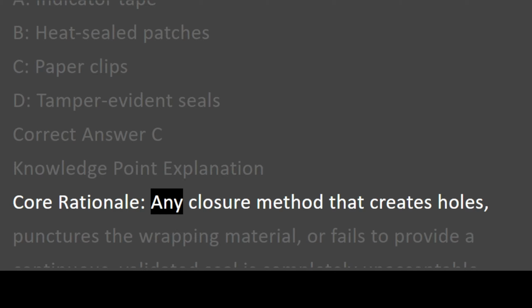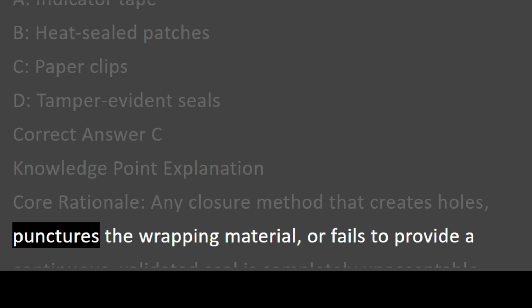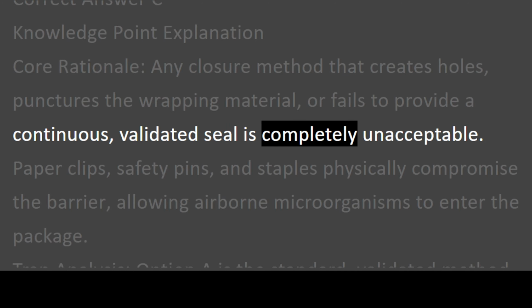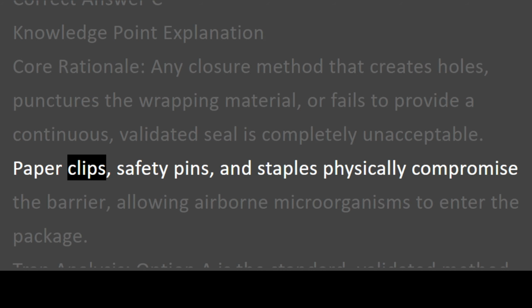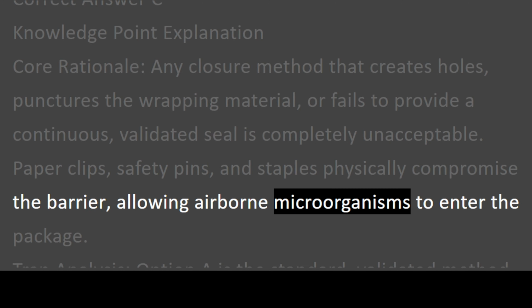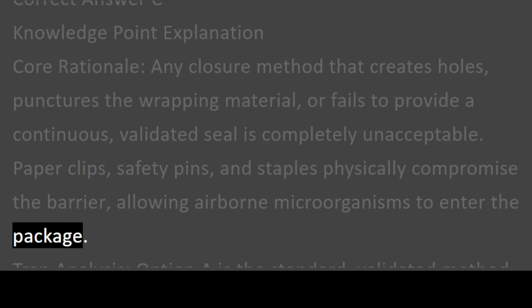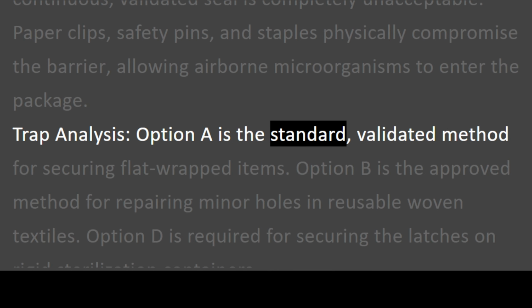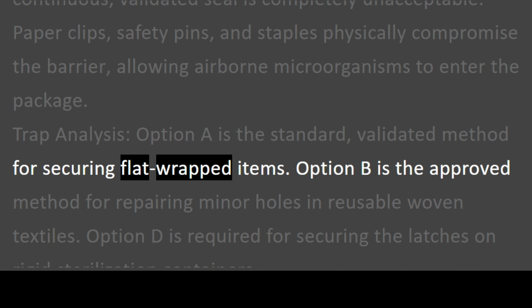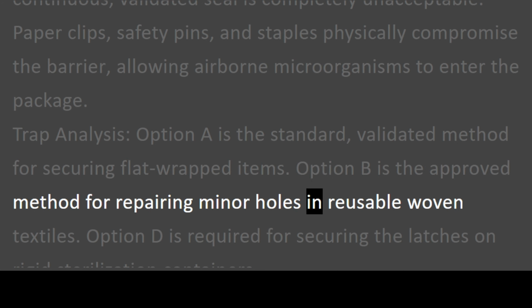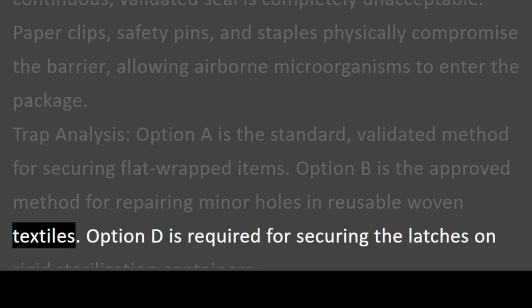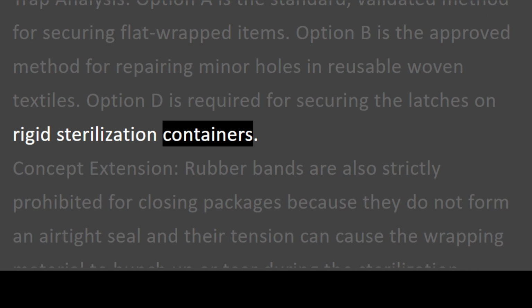Core rationale: any closure method that creates holes, punctures the wrapping material, or fails to provide a continuous, validated seal is completely unacceptable. Paper clips, safety pins, and staples physically compromise the barrier, allowing airborne microorganisms to enter the package. Trap analysis: option A is the standard, validated method for securing flat-wrapped items. Option B is the approved method for repairing minor holes in reusable woven textiles. Option D is required for securing the latches on rigid sterilization containers.